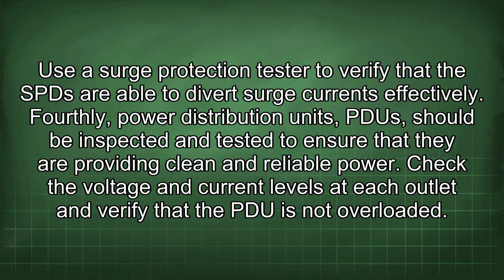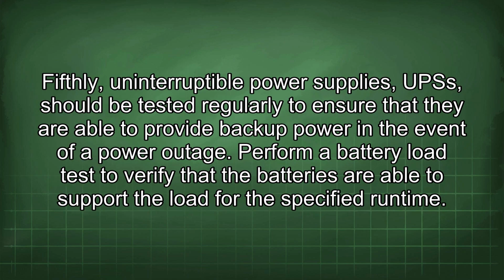Fourthly, power distribution units, PDUs, should be inspected and tested to ensure that they are providing clean and reliable power. Check the voltage and current levels at each outlet and verify that the PDU is not overloaded. Fifthly, uninterruptible power supplies, UPSs, should be tested regularly to ensure that they are able to provide backup power in the event of a power outage. Perform a battery load test to verify that the batteries are able to support the load for the specified runtime.